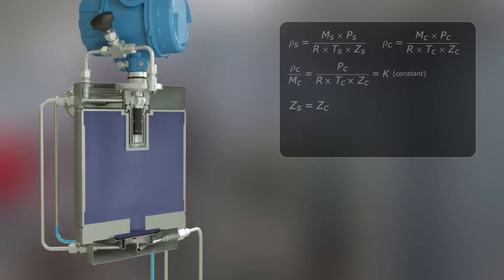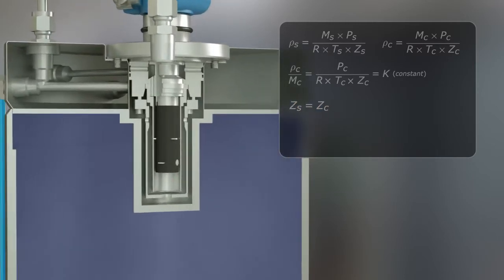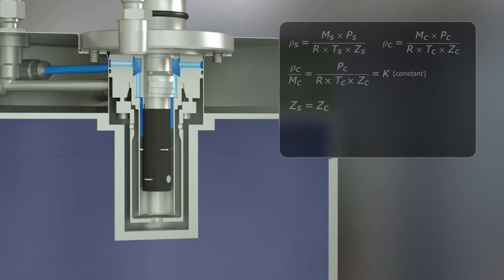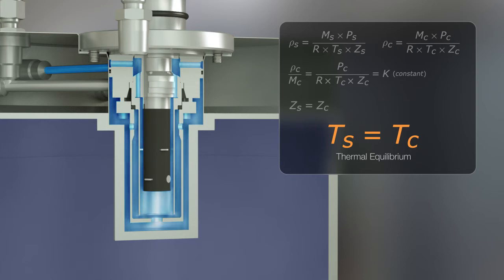After passing through the initial pipework, gas coming into the meter first flows through the sensor. The meter design and material act as a heat sink to establish thermal equilibrium between the sample and reference chamber gas.